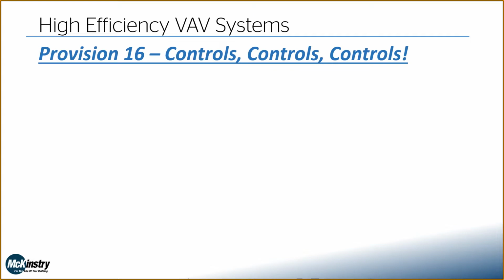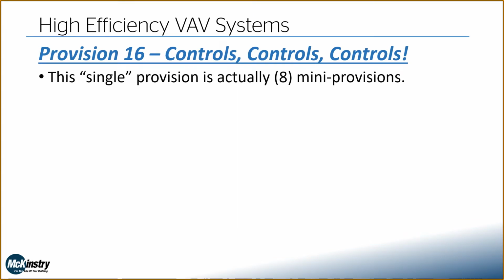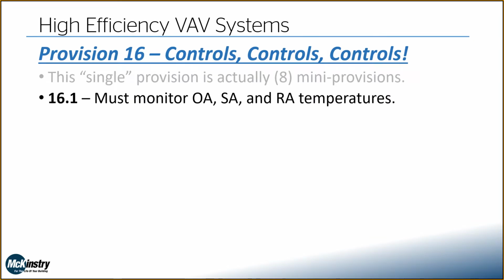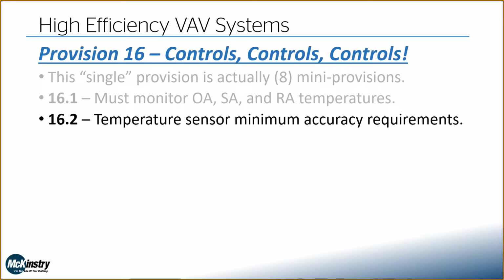The last provision, controls. So I mentioned controls was going to come back. And if you look at the code, this single provision takes up an entire page. This one provision, put in quotes, this single provision is actually 8 mini provisions. So there's 8 things that this one provision is asking you to do. We have to monitor our outdoor air, supply air, and return air temperatures. Our temperature sensors have to meet a minimum accuracy requirement, as described in the code.